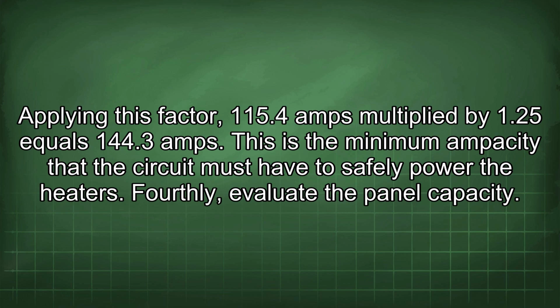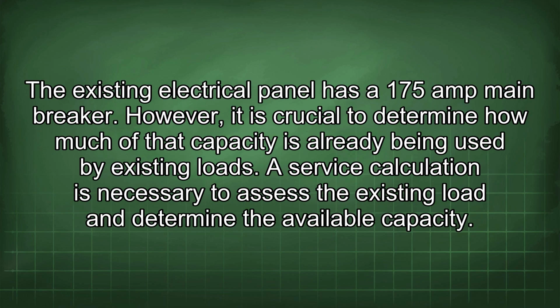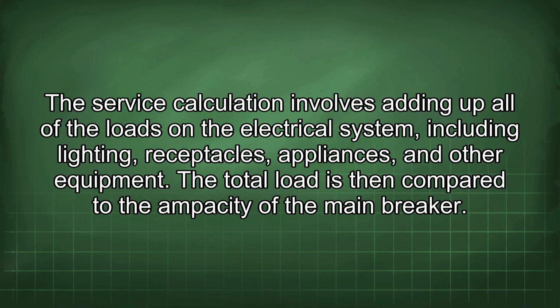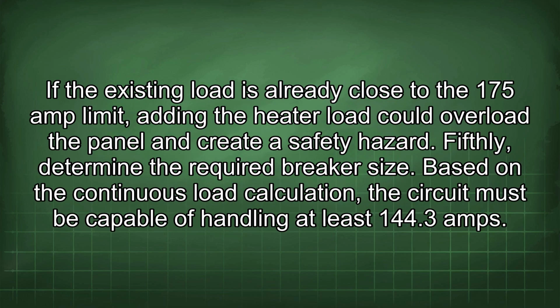Fourthly, evaluate the panel capacity. The existing electrical panel has a 175 amp main breaker. However, it is crucial to determine how much of that capacity is already being used by existing loads. A service calculation is necessary to assess the existing load and determine the available capacity. The service calculation involves adding up all of the loads in the electrical system, including lighting, receptacles, appliances, and other equipment. The total load is then compared to the ampacity of the main breaker. If the existing load is already close to the 175 amp limit, adding the heater load could overload the panel and create a safety hazard.